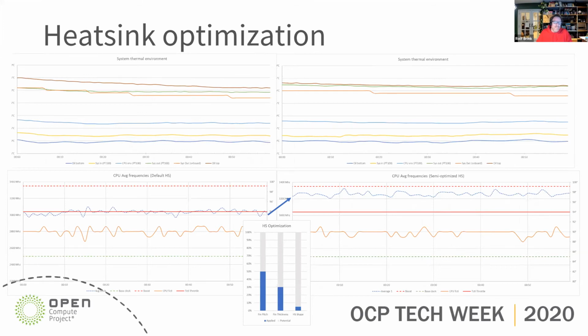One of the most fundamental advantages that can be achieved with immersion cooling is in something as simple as heatsink design. If you look at an average heatsink designed for air, you're looking at a very close positioning of fins, narrow spacing between them, and the fin thickness is usually not that big, all designed to force air through a lot of surface area.